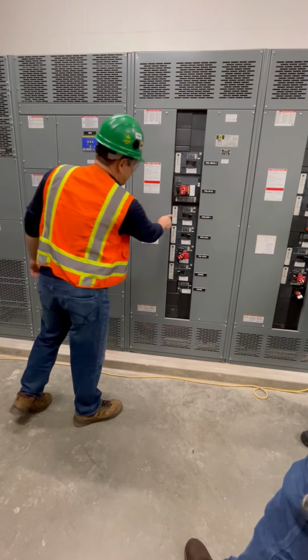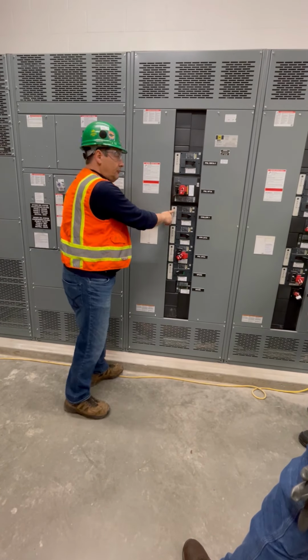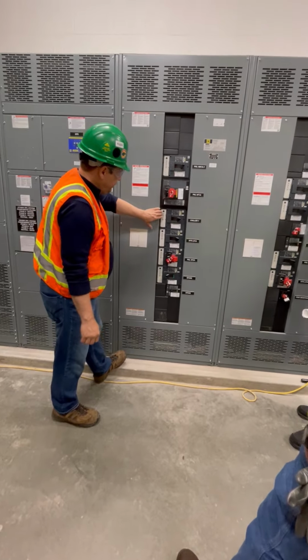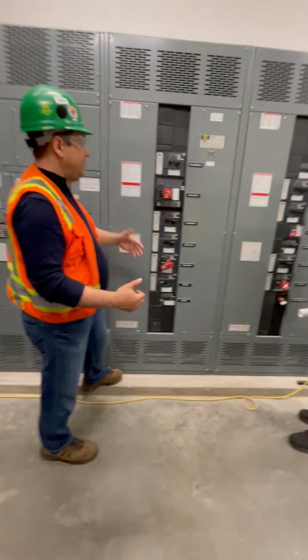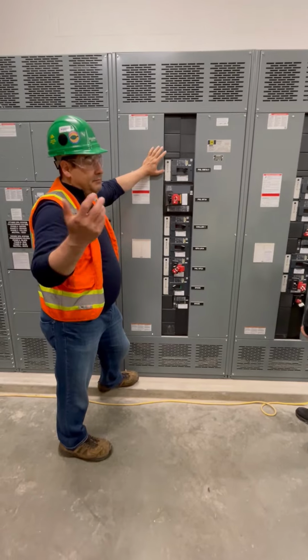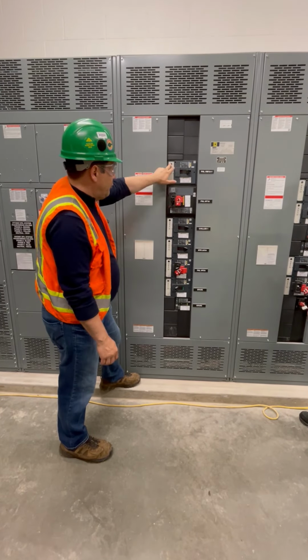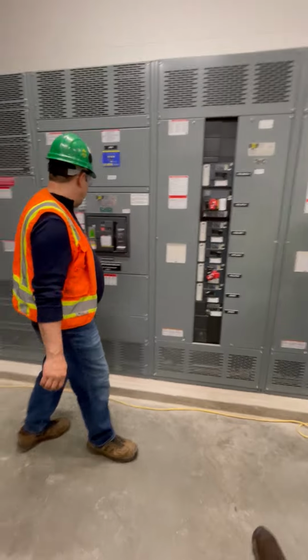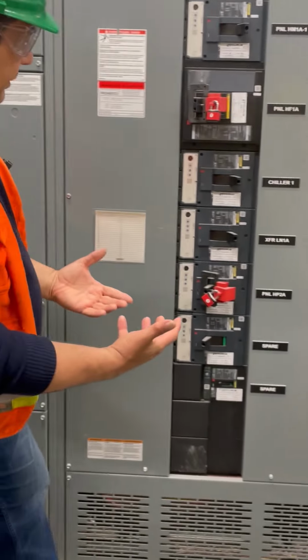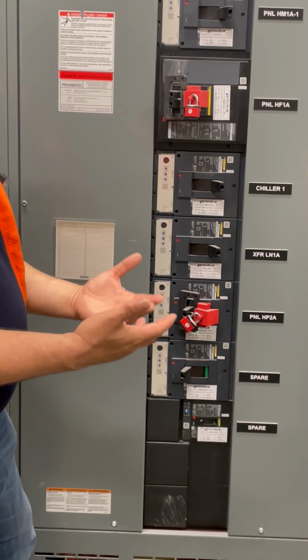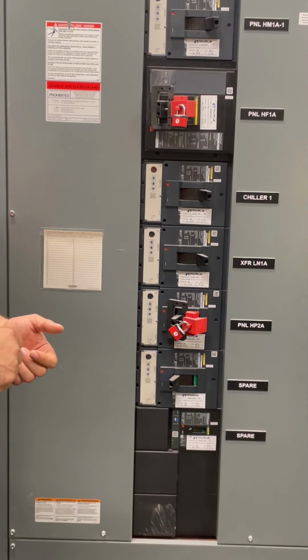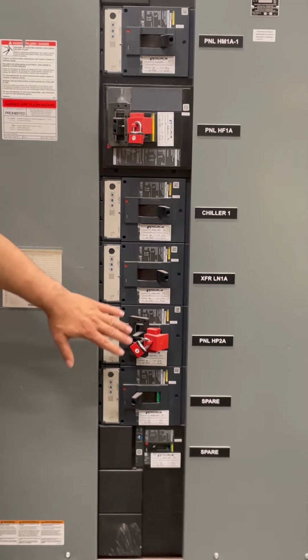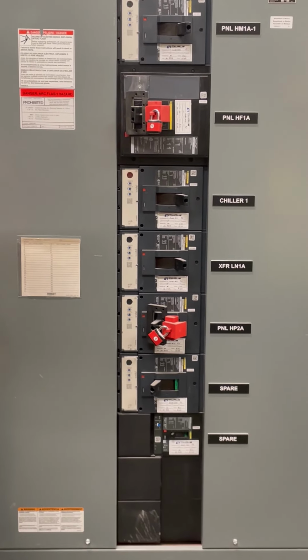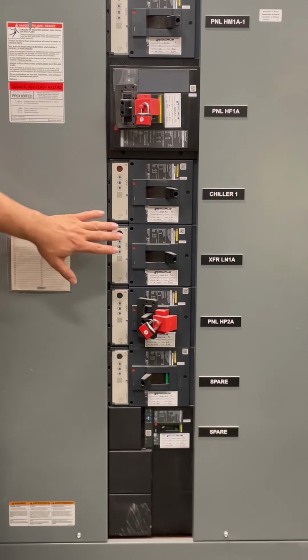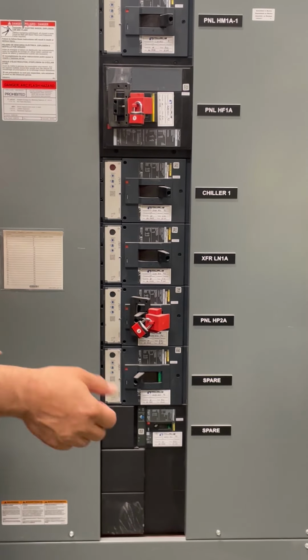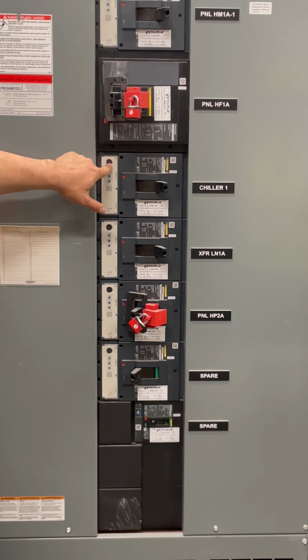This right here has the same port as these breakers here. So this is not necessarily for you unless you want to do your own maintenance. We do have test kits that some customers can purchase, and through these ports right here, or the one behind this cover here, we take the secondary injection test set, hook up to these breakers, and we can test these breakers electronically. The difference is if you do a primary injection, you have to bring in big test sets, that kind of thing. But that's what these ports are.